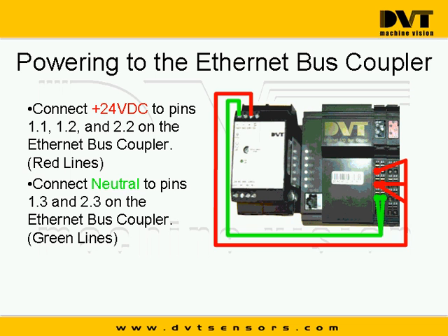And what you're going to be doing is supplying power, 24 volts in fact, to these red lines that you see here, these points of connections, and that's exactly what I have done here for my power supply. In my case, I'm actually using one power supply to supply power to everything on this Con IOE, and it works just fine the way it is now.